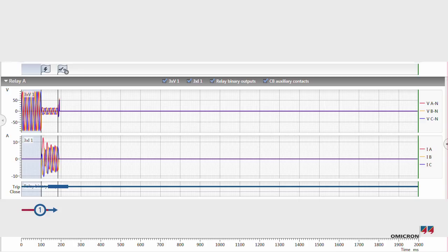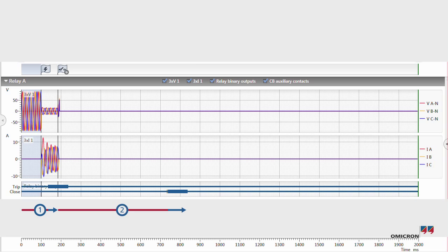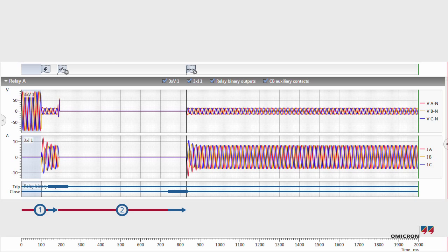The relay issues a reclose command after the dead time. Again, RelaySimtest remembers this new relay reaction and integrates it into the next iteration, simulating the reclosing of the circuit breaker and putting the fault current back on.